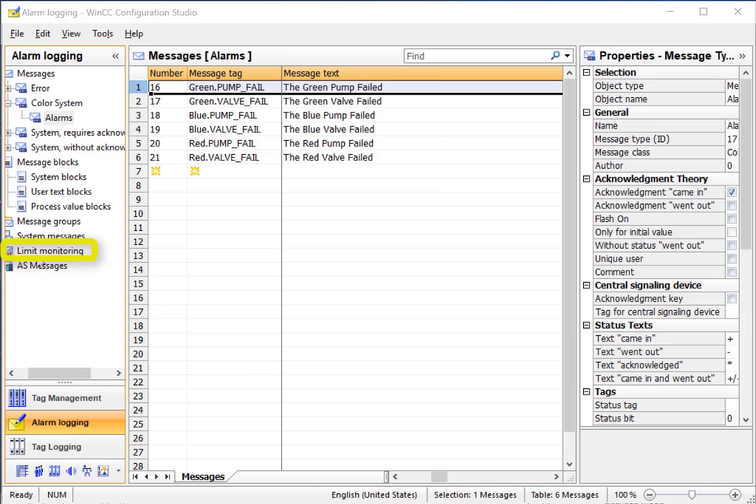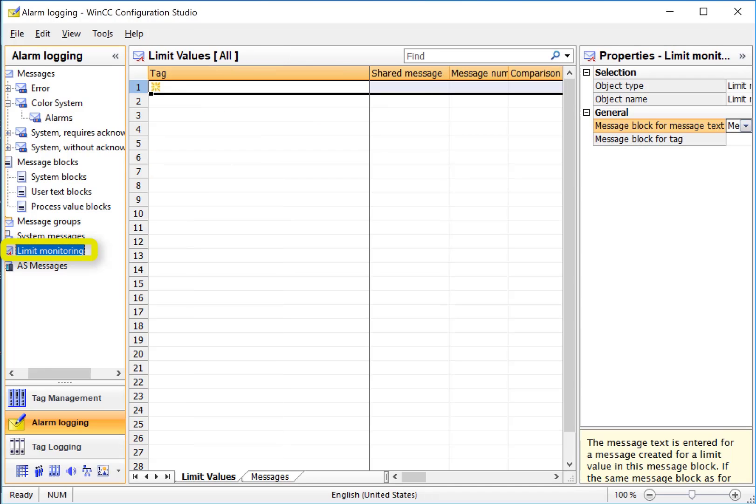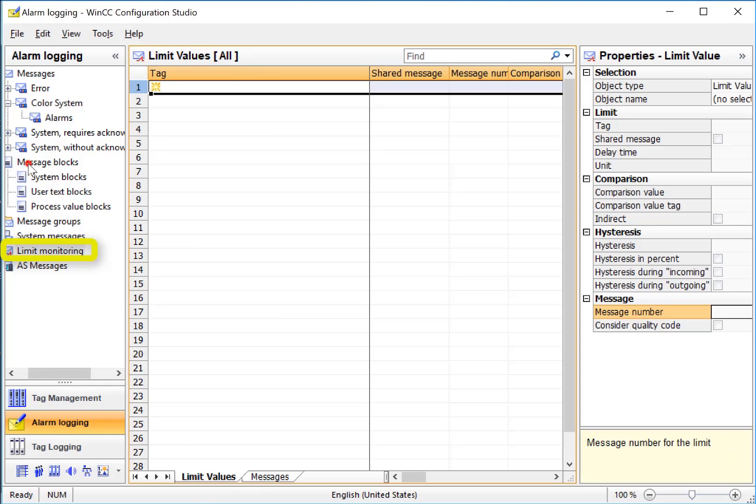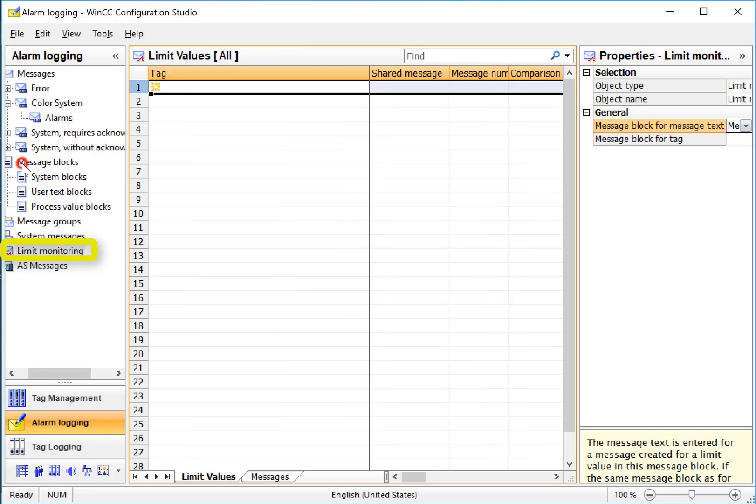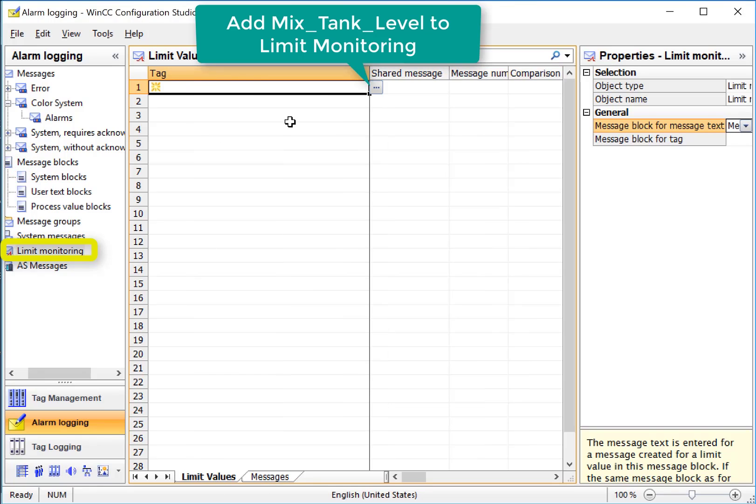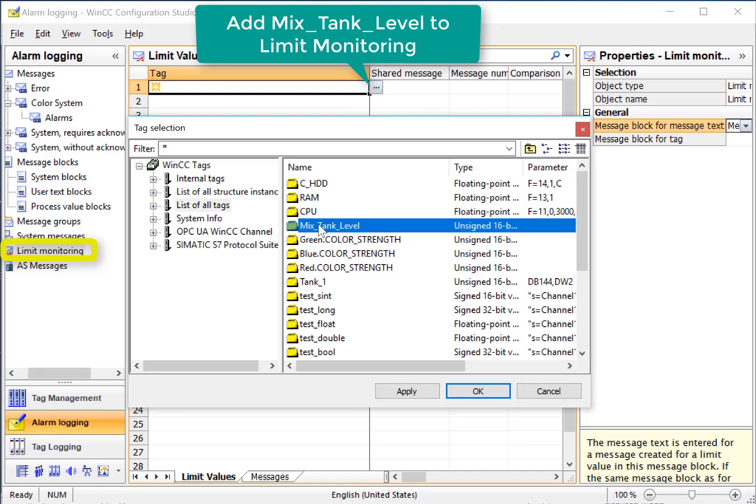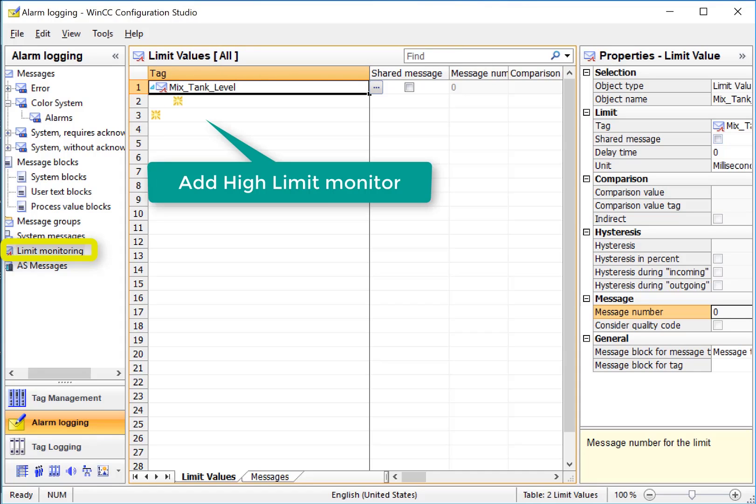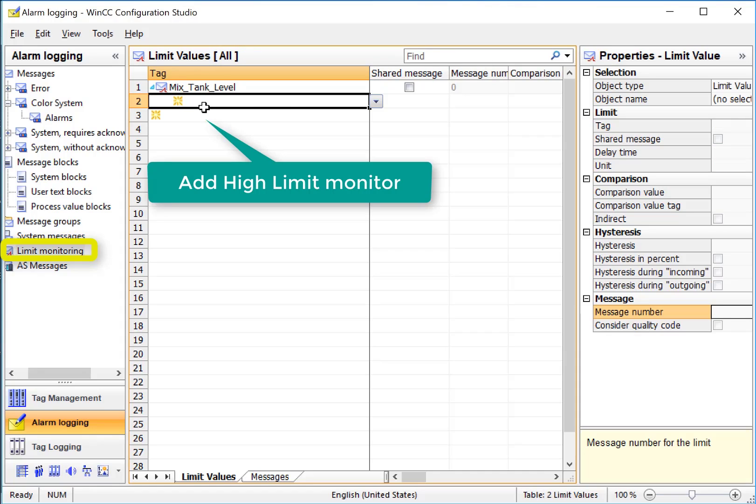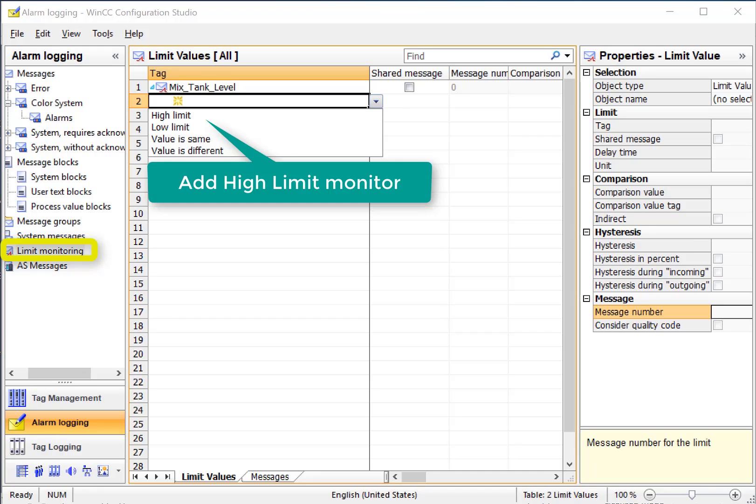Now let's create our analog alarm. We'll go to limits monitoring, and in the work area, we have a limit values tab where we associate the tag and assign high and low limits, and we have the messages tab, which is where we configure our messages. So we'll start here under limit values, and I'll add our Mix_Tank_Level. If you have a filter set, make sure you clear that, and I'll just click OK. So this is a new limit to monitor, and if we just click the triangle there, it will allow me to add high or low limits or same or different values. So I'll just set a high limit.